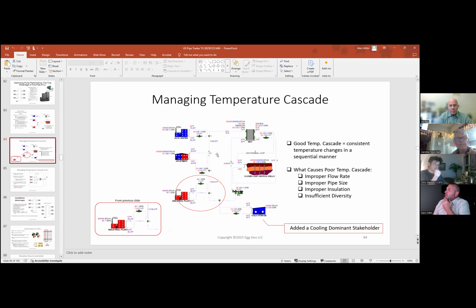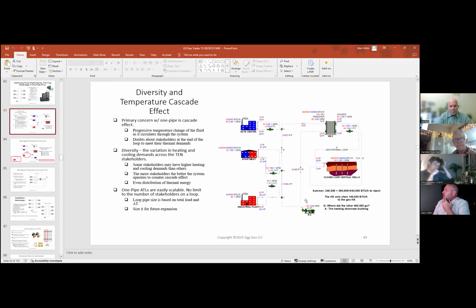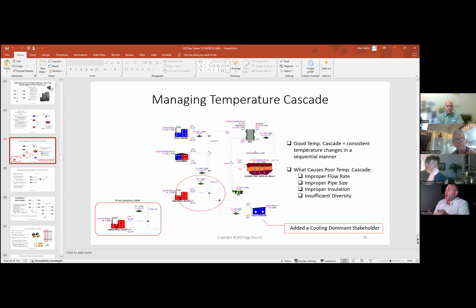Now, one thing that I want you to notice here is that we added essentially 10 tons of cooling to this, all right? Yeah, this is 20 tons. This is 10 tons right here of cooling. All right. We added 10 tons of cooling, but look at our pipe size. It's still 3-inch. All right. There's no change. All right. Now, what did change is this pump, the GPM that this pump is moving now. See, 52 GPM in summer. If we go back here, what was it moving with just 28 GPM. So the system responded because it's pump controlled. All right. So the pump sped up to accommodate this new stakeholder on the loop.